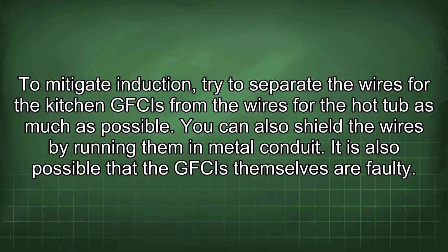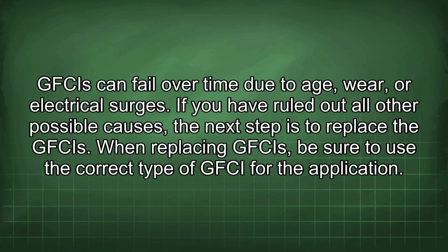It is also possible that the GFCIs themselves are faulty. GFCIs can fail over time due to age, wear, or electrical surges. If you have ruled out all other possible causes, the next step is to replace the GFCIs. When replacing GFCIs, be sure to use the correct type of GFCI for the application.